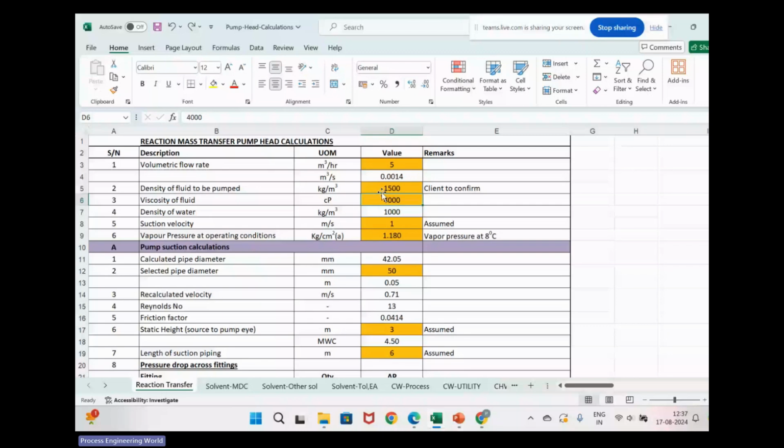Why will you not get the viscosity of the fluid from an Ostwald? Yes, Ostwald is also used, but generally Brookfield has an accuracy of plus minus 0.1, and Ostwald has an accuracy of plus minus 0.5. Plus minus 0.5 is also quite small, but industries still prefer Brookfield because, from a maintenance and service point of view, the Brookfield viscometer is quite good compared to Ostwald. So you will get the viscosity of the fluid.